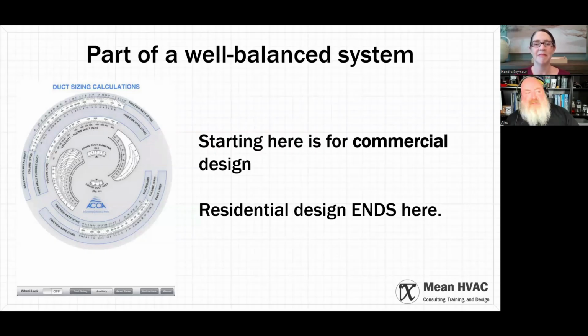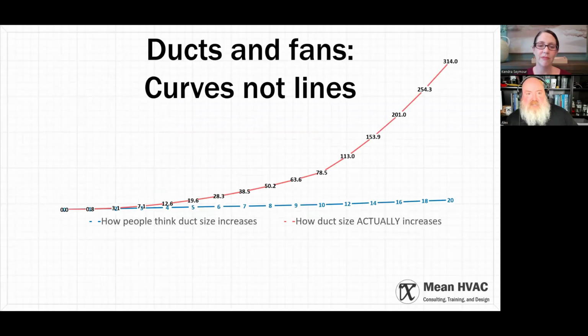So you have to think about changing how you do ductwork to accommodate different situations. And if you're attempting any of this on your own, you need to understand that ducts and fans behave on a curve, not on a line. It's easy to think, oh, it's just a 6 or a 7, it's a 28 or a 38, because air goes through the whole middle of the duct. It's not the diameter that matters, it's the cross-sectional area.